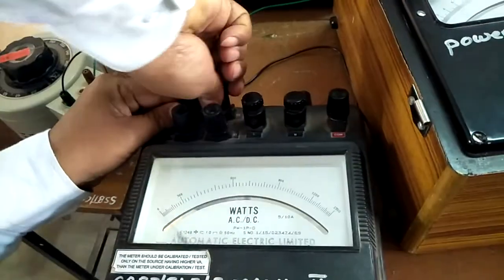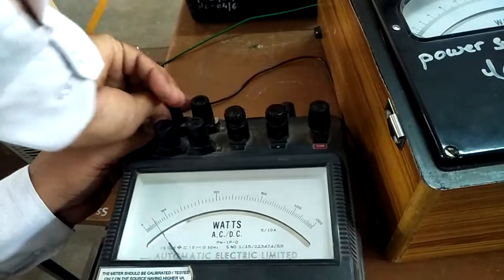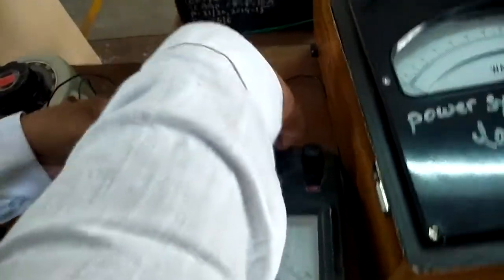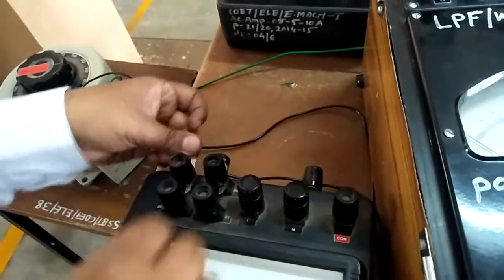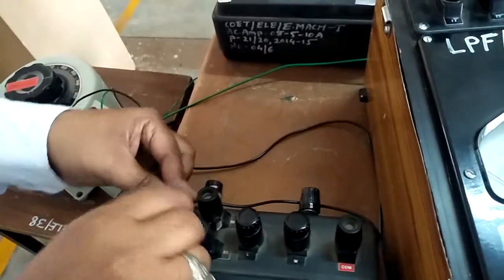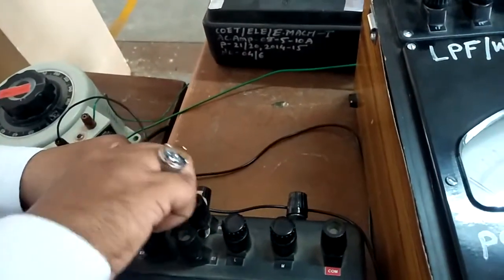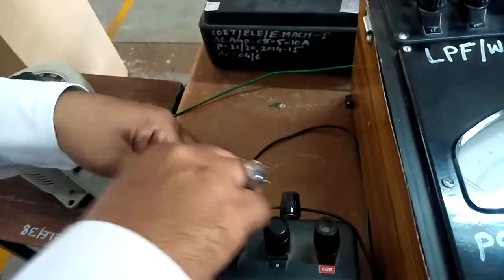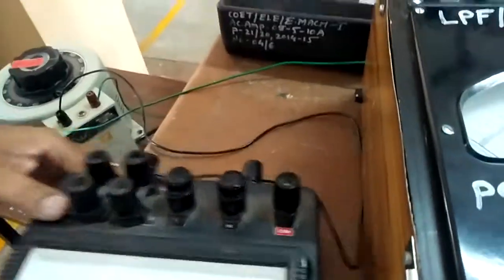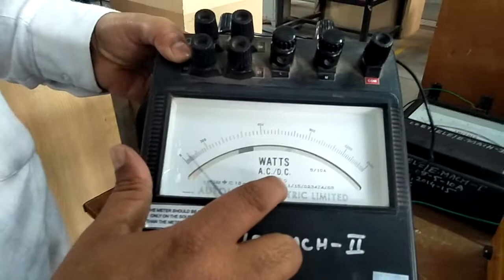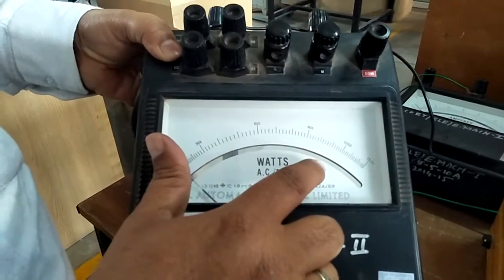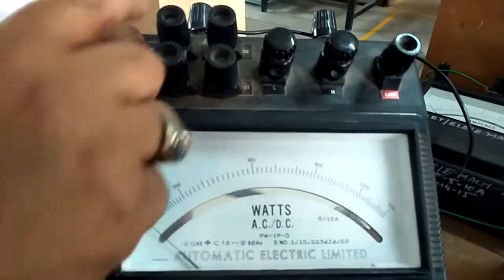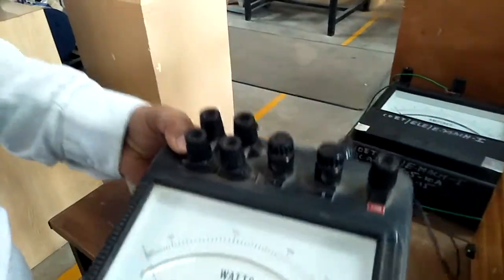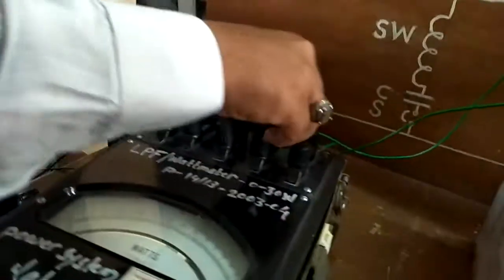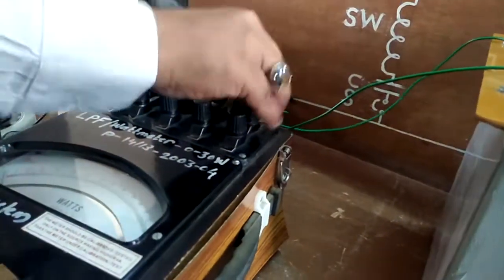So we will change to the parallel one. So now B1 is connected to E2. So it is in parallel, the higher range of current. See, in this case it is written as 5 ampere and 10 ampere. So for 10 ampere you have to make it parallel, okay, and otherwise it will be in series. So now replace the connections.